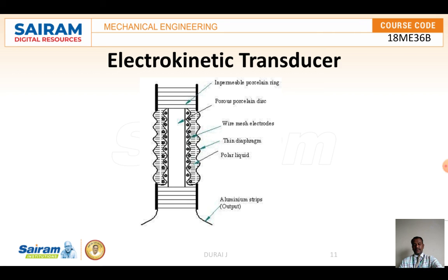When the direction of the flow is reversed, the polarity of the electrical signal is also reversed. An unlimited supply of liquid is required upstream to measure the static differential pressure with this kind of electrokinetic pickup. This is impractical with the finite amount of liquid contained in the electrokinetic cell.